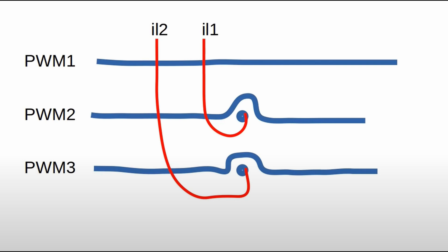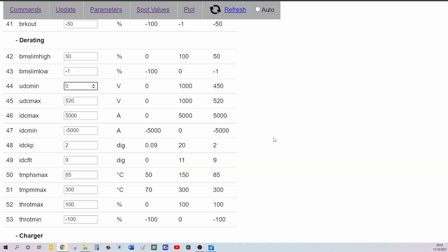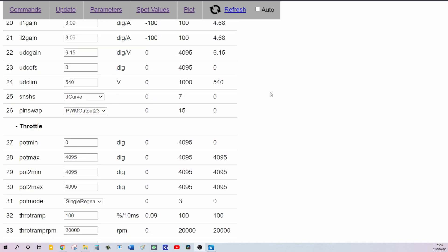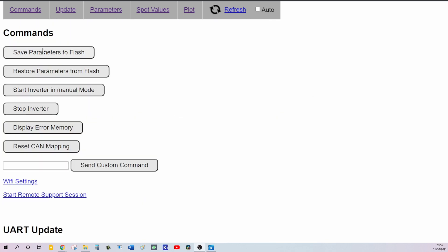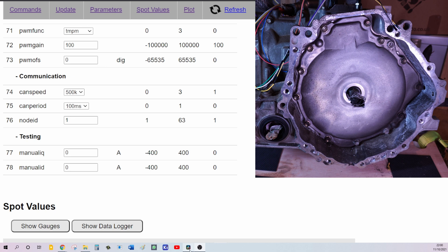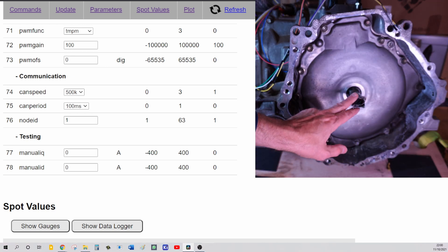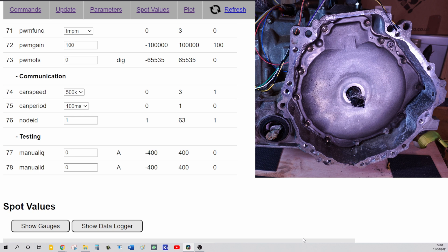To finish off, I need to set UDC minimum to zero as my voltage is only 60 and change the temperature maximum to 150. The last thing I need to do is just to save the parameters to flash. I removed my pliers so that this one will not jam into anything and just entered manual ID 1 amp.